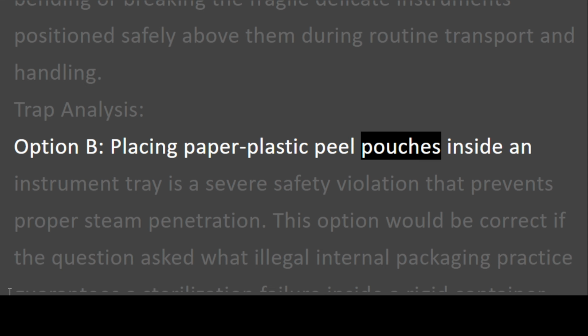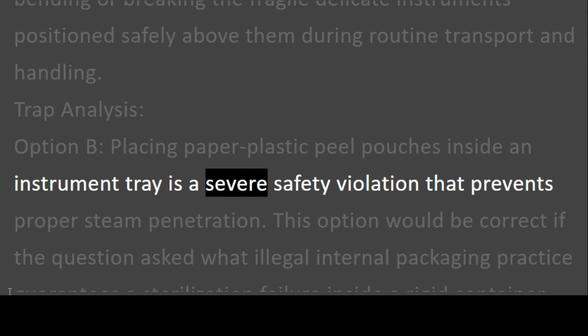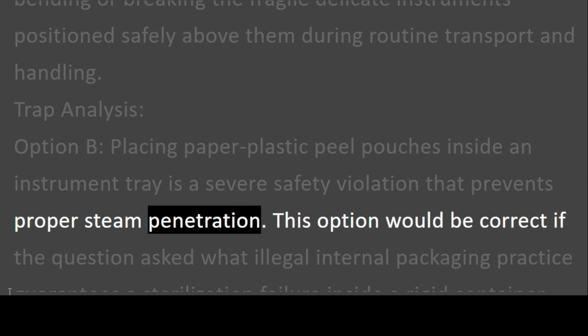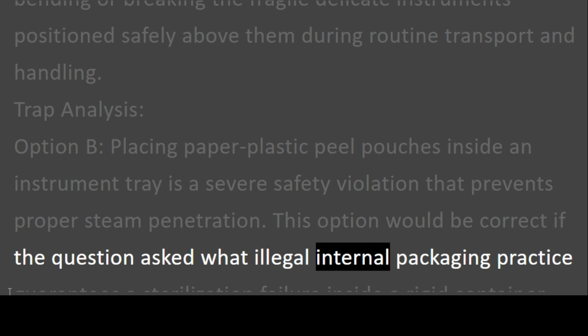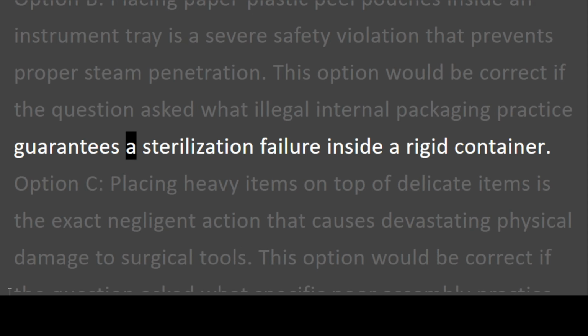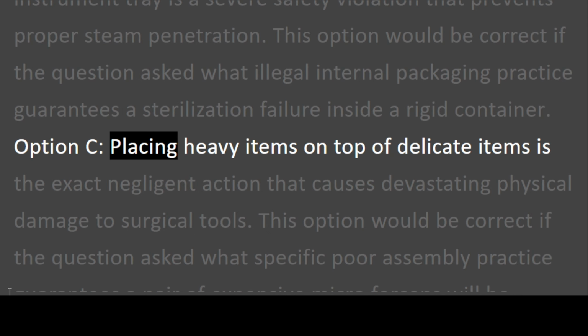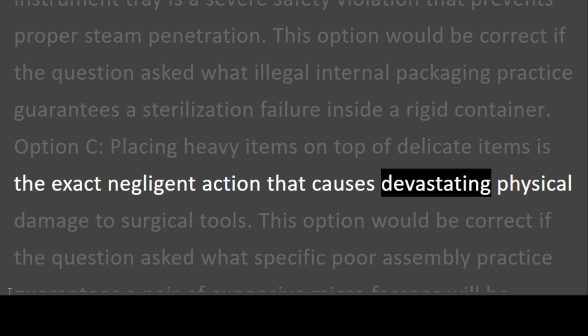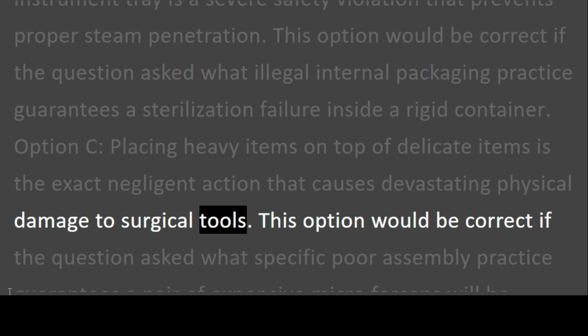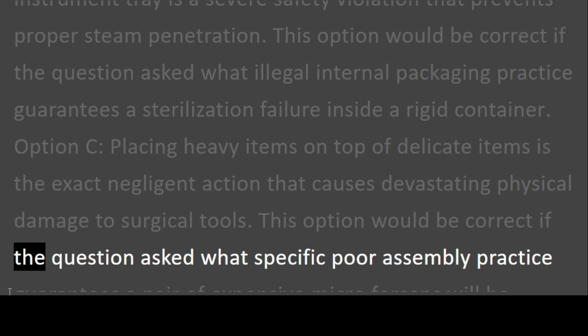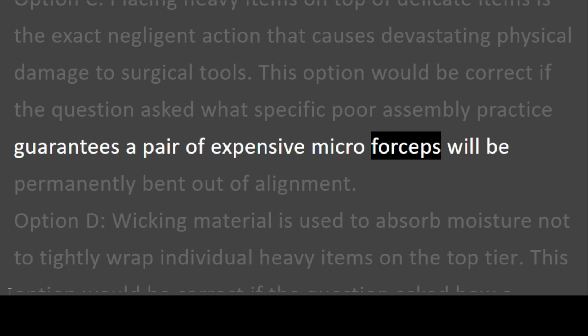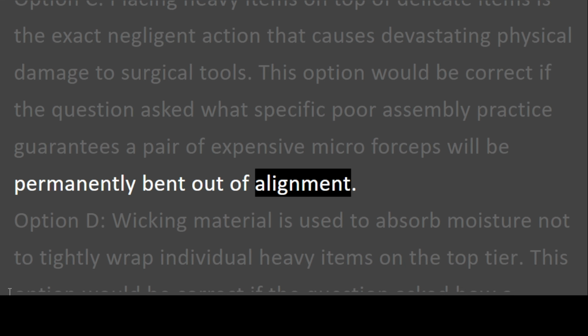Placing paper plastic peel pouches inside an instrument tray is a severe safety violation that prevents proper steam penetration. This option would be correct if the question asked what illegal internal packaging practice guarantees a sterilization failure inside a rigid container. Option C. Placing heavy items on top of delicate items is the exact negligent action that causes devastating physical damage to surgical tools. This option would be correct if the question asked what specific poor assembly practice guarantees a pair of expensive micro-forceps will be permanently bent out of alignment.